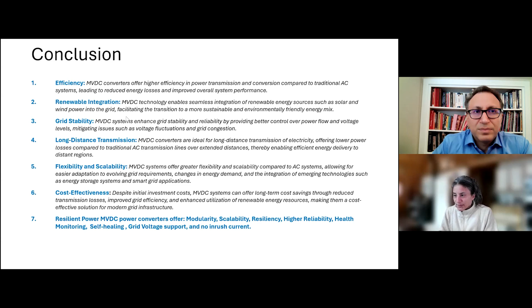I'll also point out that when we did this case study looking at an intertie between Ambler and Shungnak, it had actually been looked at before. But honestly, the biggest challenge was finding a technology provider able to supply equipment at the voltage and power levels relevant for rural Alaska. Most commercial products today are much higher voltage, greater than tens of kV, with a minimum size around 30 megawatts. To my knowledge, RPS is the only one with a commercial product in the range relevant for a rural intertie, so we were lucky to hook up with them.